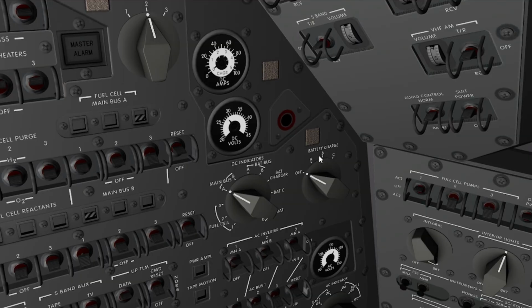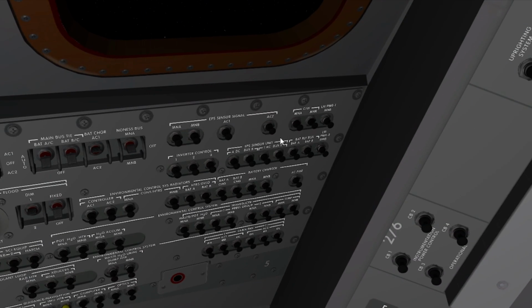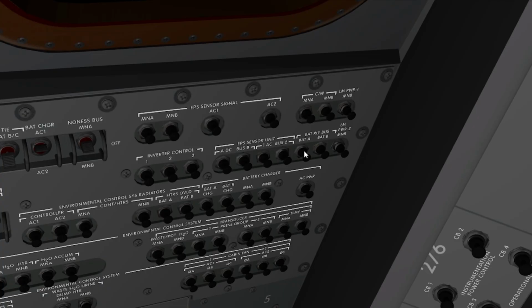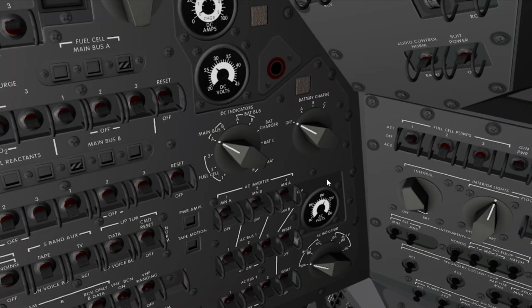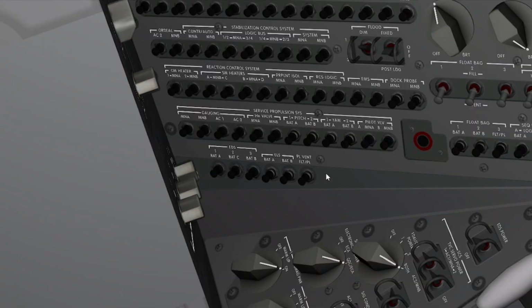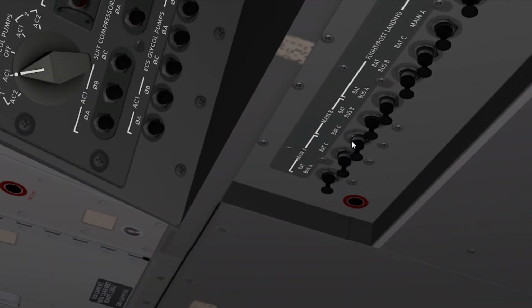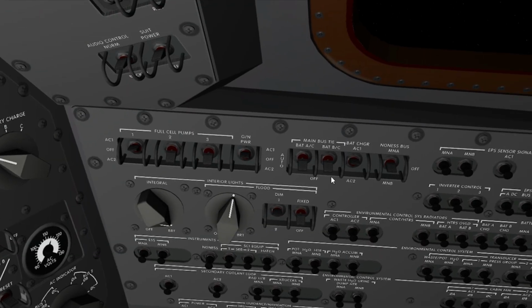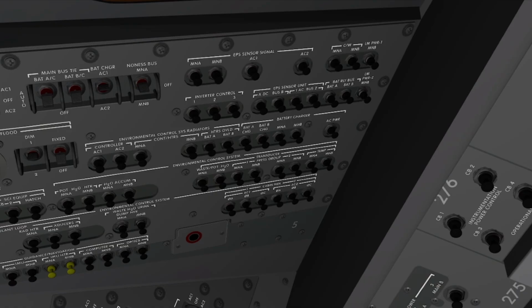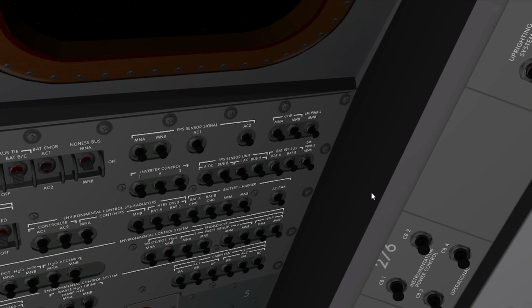But when we go to charge A or B, we want to make sure we're not drawing from the battery a whole ton either. So we'll open the battery relay bus corresponding to that battery just to make sure we're not drawing more than we need. Of course, there are battery circuit breakers that will be maintained closed, but with the bus ties off, there's really going to be nothing except the battery relay bus.